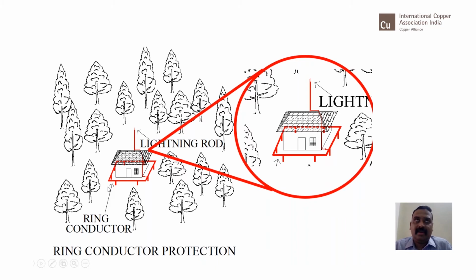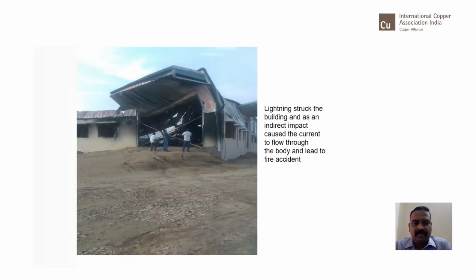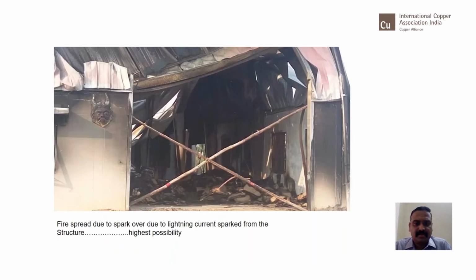So this kind of building, or special kind of areas, cannot stop only with a conventional vertical terminal and down conductor. A measure such as increasing the ring earthing around the building can reduce electromagnetic interference penetrating inside the building. So these kinds of specific designs are also to be practiced, which is an important point here. So this case study we have seen just before.